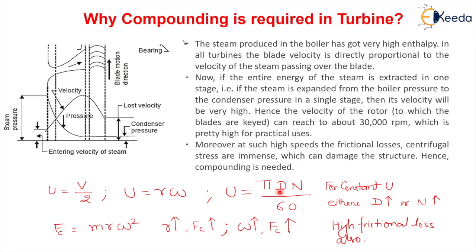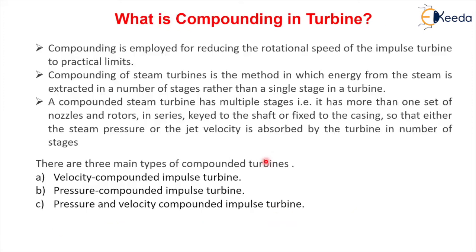We cannot increase the diameter due to space constraints, so we must increase N. But centrifugal force Fc = mrω², and as N increases, ω increases, so Fc increases. In the simple impulse turbine there will be very high centrifugal stress. Since velocity of steam is very high on the turbine blades, frictional loss will also be very high. Because of these conditions it can damage the structure of the steam turbine — hence compounding is needed.